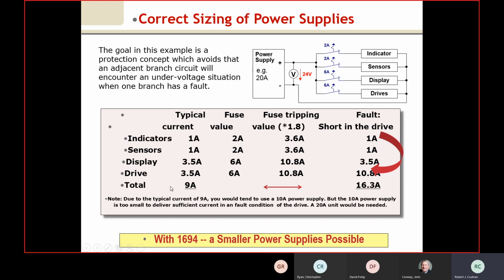So what happens in a plant is the maintenance person opens the panel, sees the red light on the power supply, goes to the tool crib and pulls a power supply, or has one ordered and has their local provider supply it as quickly as possible. Now it's installed, and when the unit is rewired and powered up again, we don't know how much time was lost, but there's downtime and lost production. They power it up only to find it was a shorted drive, but to find that shorted drive, they have to unwire each device from the unit and test it individually. So a lot of wasted time here.